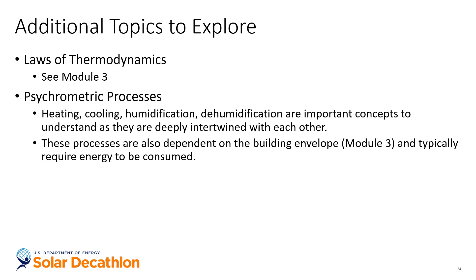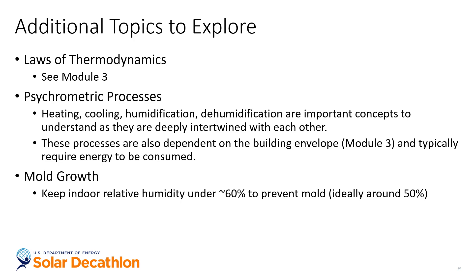A key goal for buildings is to keep occupants comfortable. The building envelope is the first line of defense, and effective envelope design is key. What the envelope cannot accomplish is left to the HVAC system, but that takes energy, and we're trying to minimize the energy impact of buildings. We also didn't discuss how temperature and humidity affect the building itself — mold growth is a risk when humidity levels remain high for too long. A general rule of thumb is to keep indoor relative humidity below 60% to prevent mold growth, though there is more complexity to this.